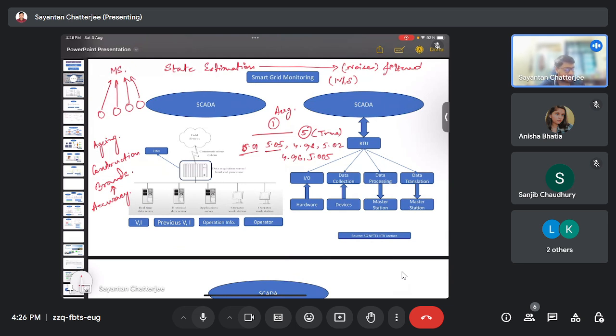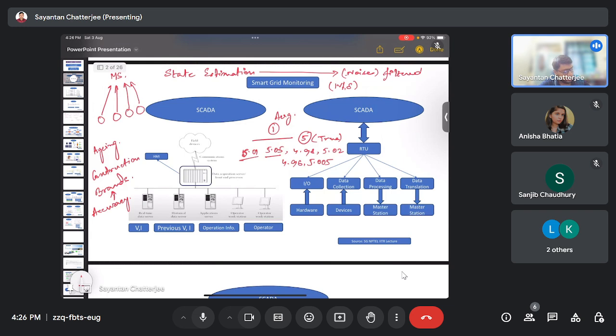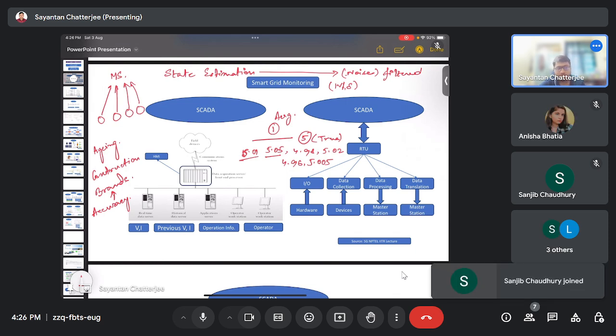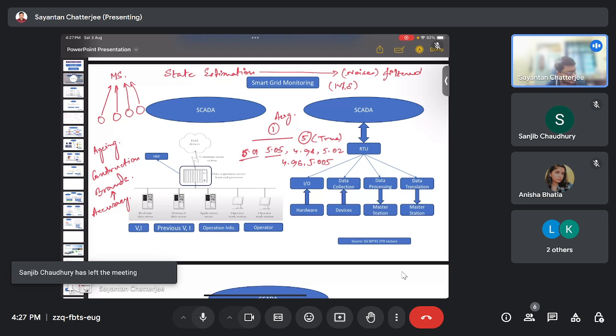In the present context, PMUs are also there, but let's consider only RTUs, because mostly RTUs are prevalent in the system. Based on these RTUs we use the WLS estimator. That's the importance of using this data, because we cannot use the data directly. We need to remove the noise, which is based on the weight, ensuring all these criteria are assigned to the minimization problem. After that we find the best possible operating states of the system. That is the use of the SCADA system or metering devices for smart grid monitoring.